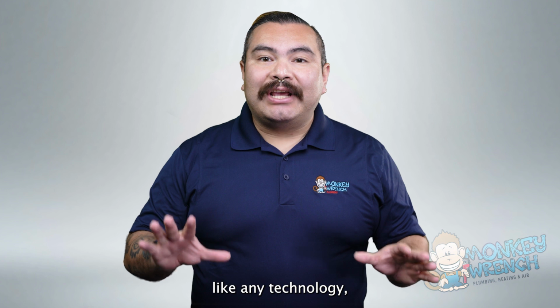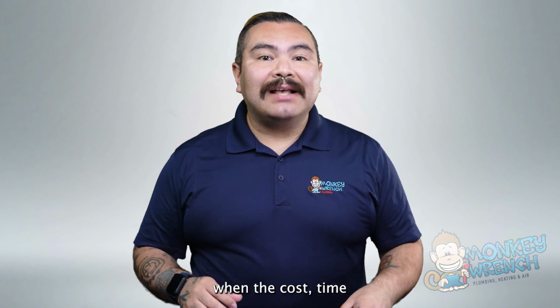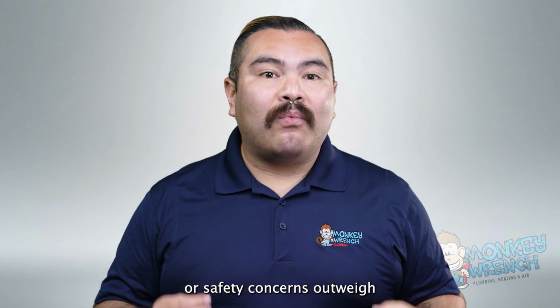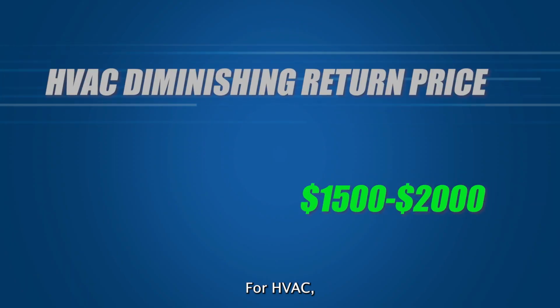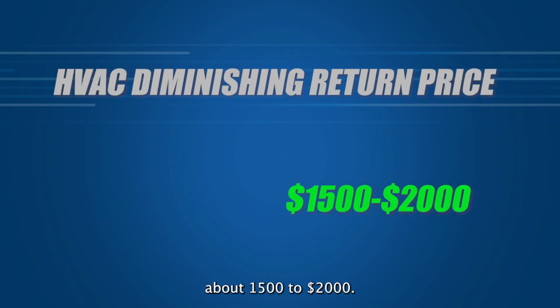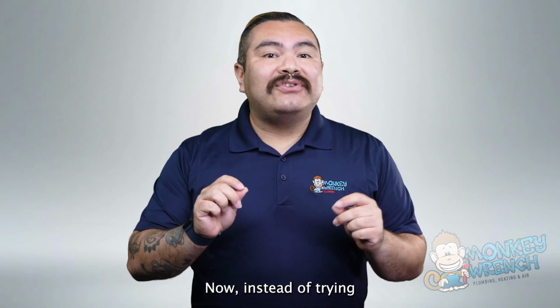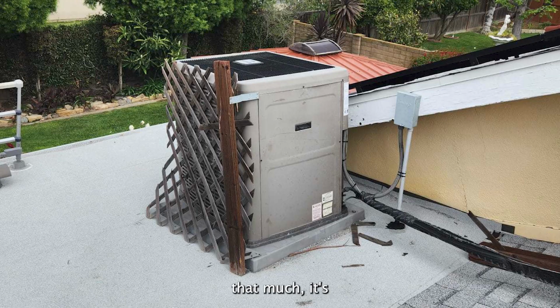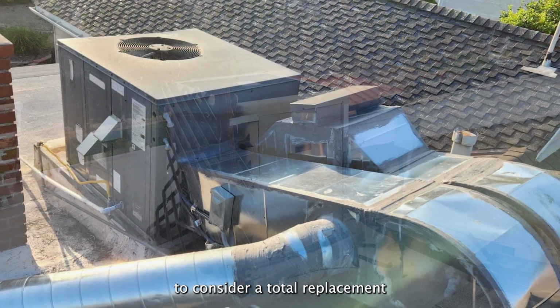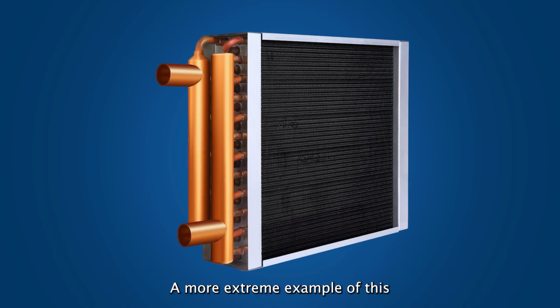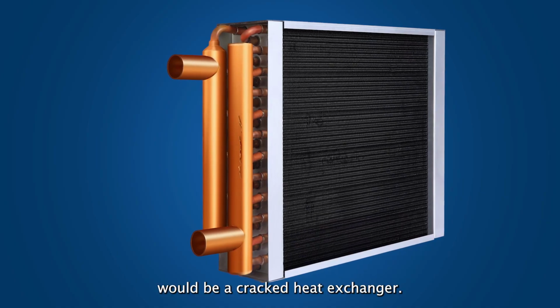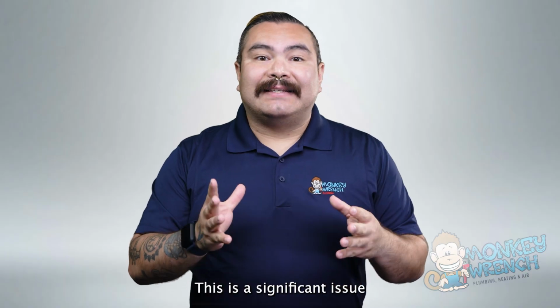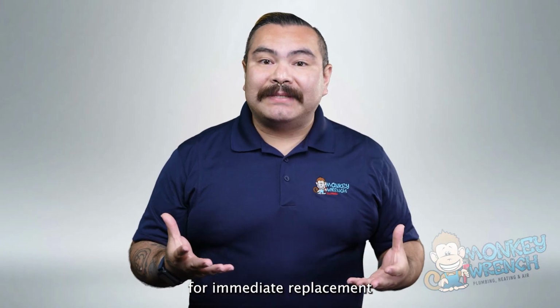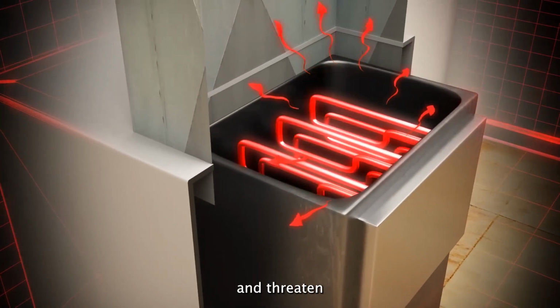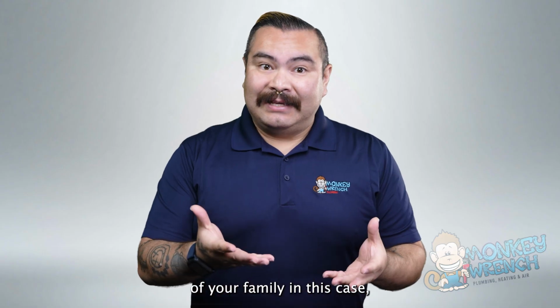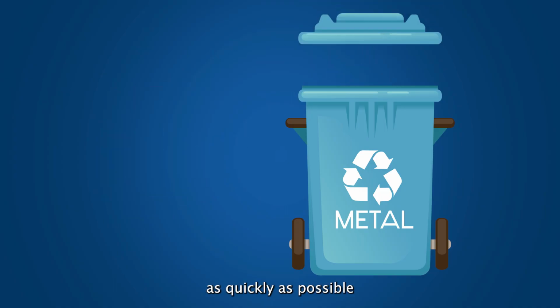Like any technology, there's a point of diminishing returns when the cost, time or safety concerns outweigh the effort required for repair. For HVAC, this would be when the repairs hit about $1,500 to $2,000. Now, instead of trying to save a part that will cost you that much, it's often in your best interest to consider a total replacement rather than a repair. A more extreme example of this would be a cracked heat exchanger. This is a significant issue that calls for immediate replacement because it can leak carbon monoxide and threaten the well-being of your family. In this case, you'd want to get that thing out of your home as quickly as possible for peace of mind.